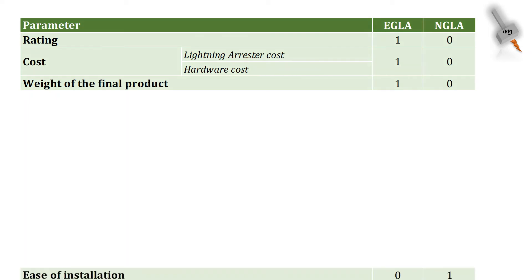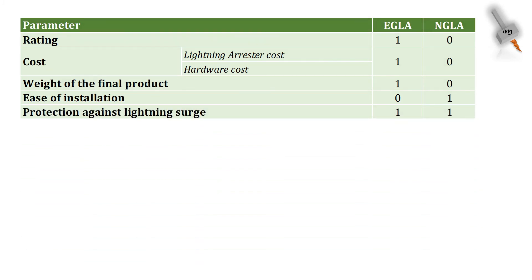In terms of ease of installation, NGLA has the advantage over EGLA since it is easy to install NGLA regardless of the new or old transmission lines. In terms of protection against lightning surge, both EGLA and NGLA has the same level of advantage, but at the same time for switching and TOV protection, NGLA has the advantage.